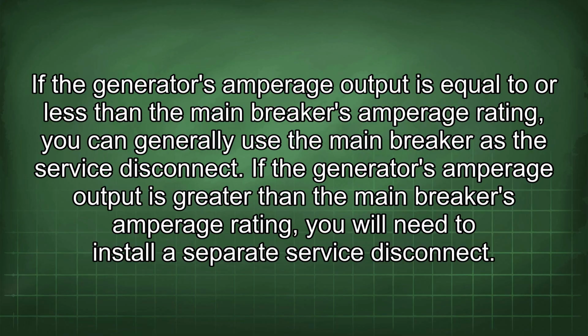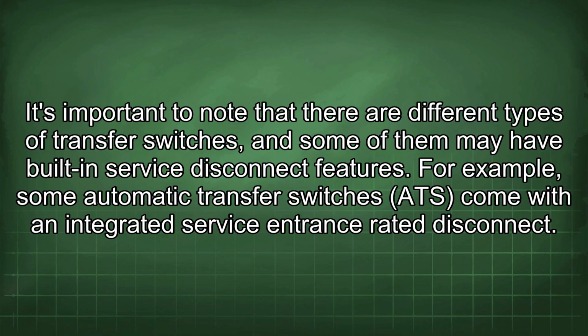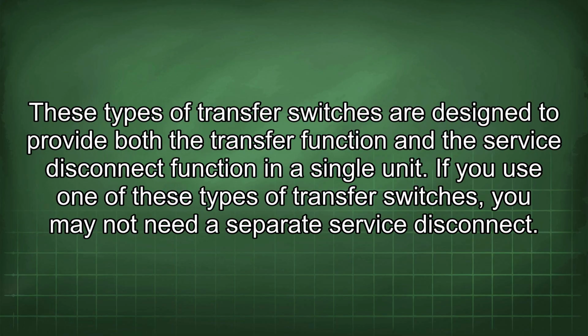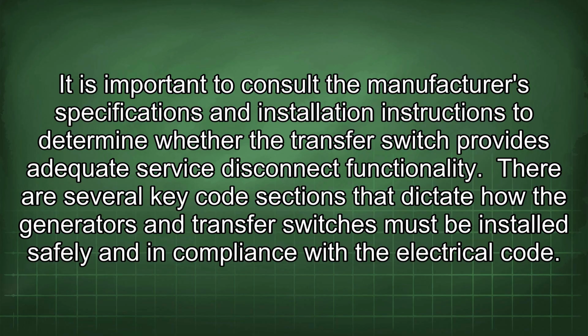It's important to note that there are different types of transfer switches, and some of them may have built-in service disconnect features. For example, some automatic transfer switches (ATS) come with an integrated service entrance rated disconnect. These types of transfer switches are designed to provide both the transfer function and the service disconnect function in a single unit. If you use one of these types of transfer switches, you may not need a separate service disconnect. It is important to consult the manufacturer's specifications and installation instructions to determine whether the transfer switch provides adequate service disconnect functionality.